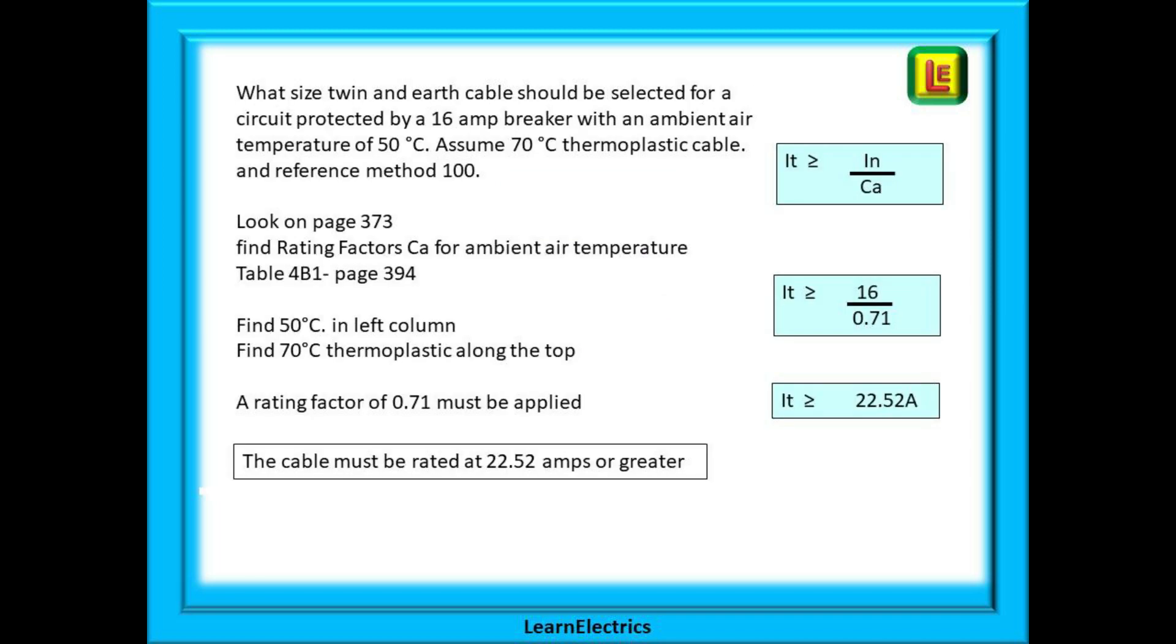If a question asked what size twin and earth cables should be selected for a circuit protected by a 16 amp breaker with an ambient air temperature of 50 degrees centigrade. Assume 70 degrees centigrade thermoplastic cable and reference method 100. We can begin by looking on page 373 and find the rating factors CA for ambient air temperatures.